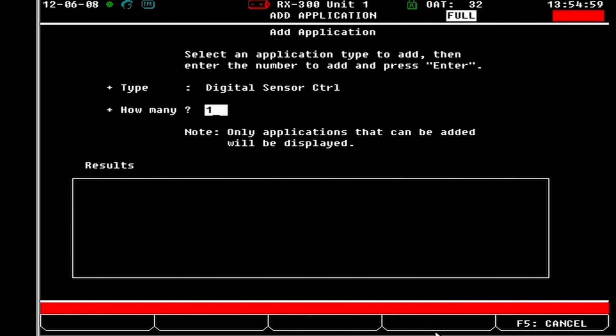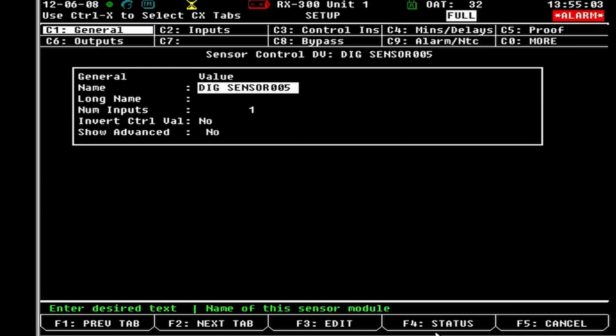Now the difference between a digital sensor control and an analog sensor control is a digital sensor control is going to be on or it's going to be off. Whereas an analog sensor control is going to have a varying signal, whether it be voltage, current, temp sensor, anything like that. Anything that varies is going to be analog. Anything that's on or it's off is going to be digital. So whether it's a physical switch, a defrost termination, level, anything in the controller that is on or it's off, whether it be a physical board point or it's a networked variable.